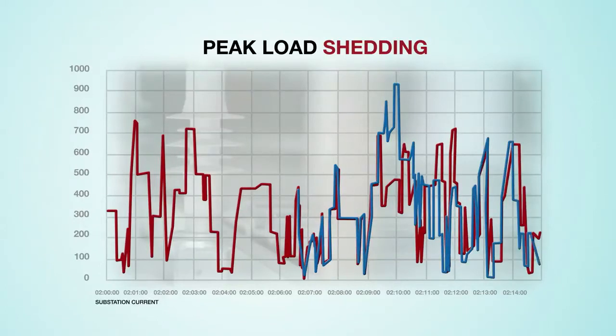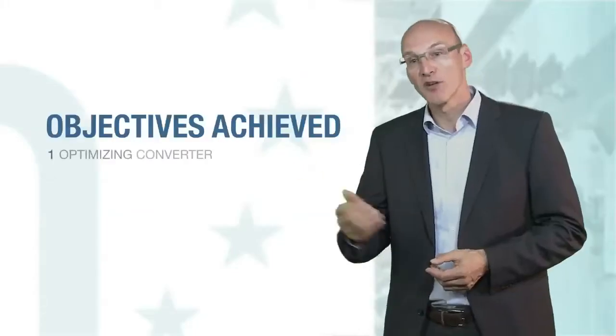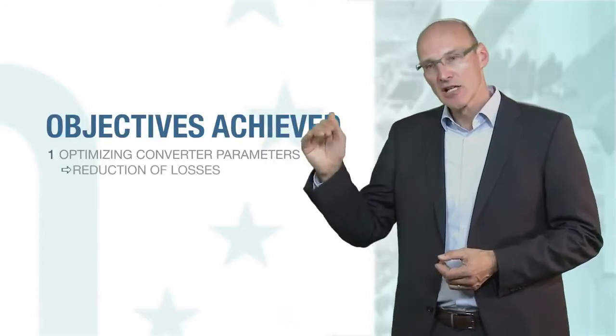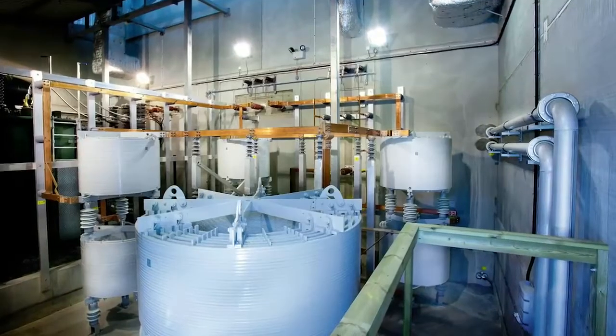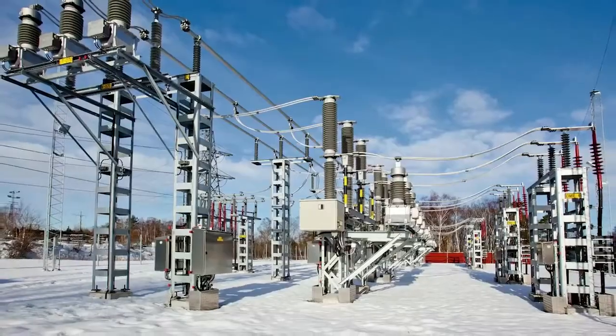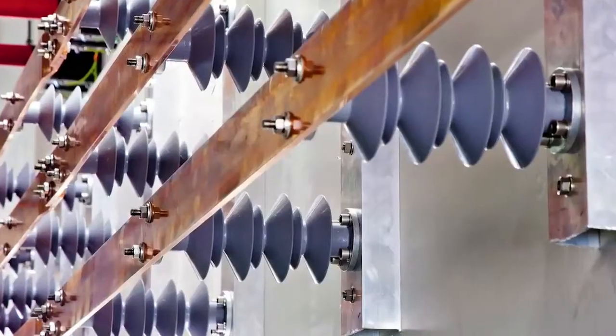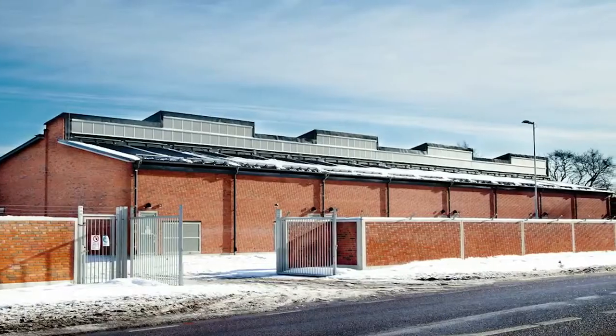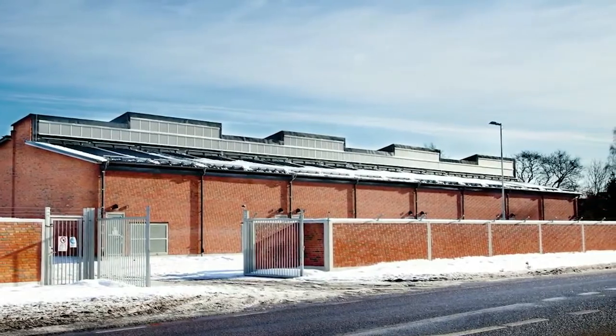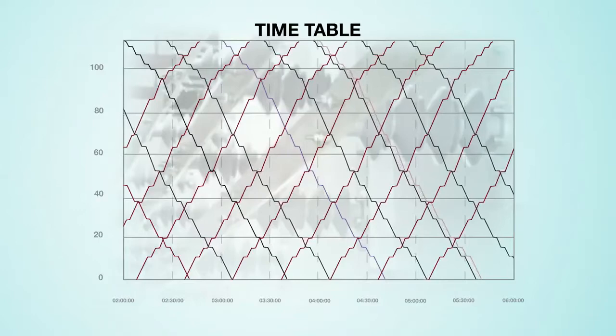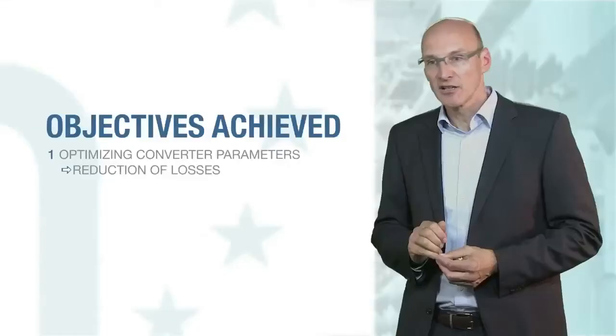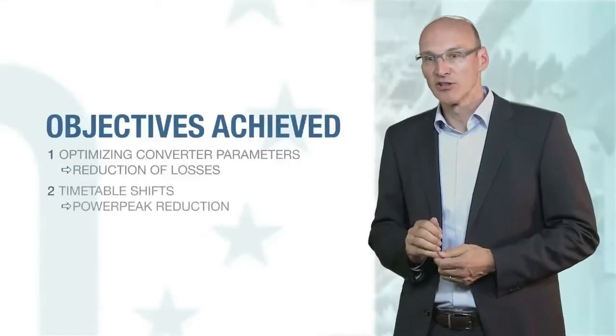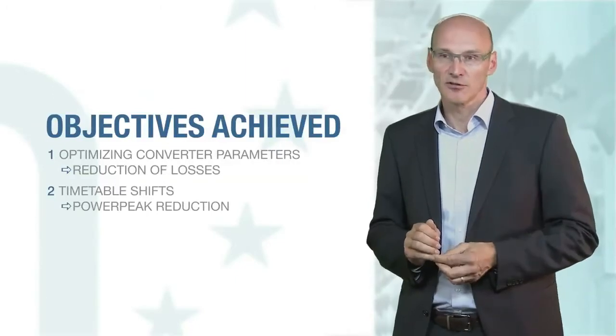The conclusion: both targets could be reached by optimizing the converter parameters. The energy flow in the system can be optimized, and also the energy demand could be reduced, so losses could be reduced. The second subject looks very promising, and I think it's demonstrated quite well that only short modifications in the timetable can reduce the power peaks, and then the goal of Trafikverket can be reached by that.